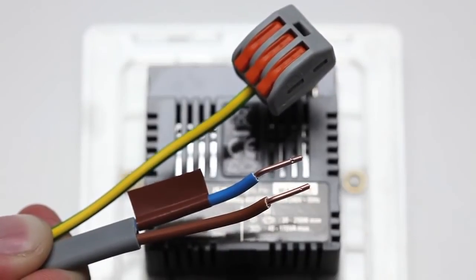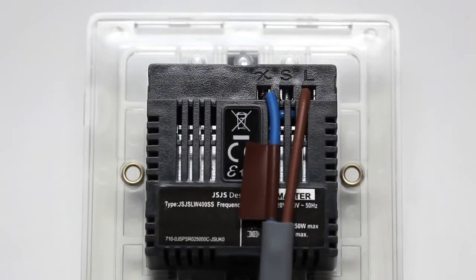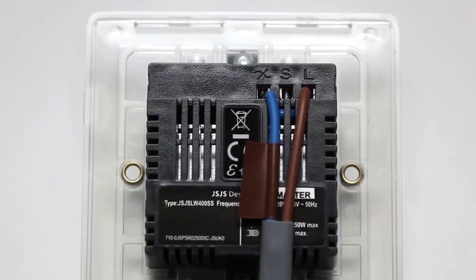The dimmer switch is double insulated, so doesn't need to be earthed directly. The switched live wire in may be marked by brown or red tape to emphasise that it's not a neutral wire.